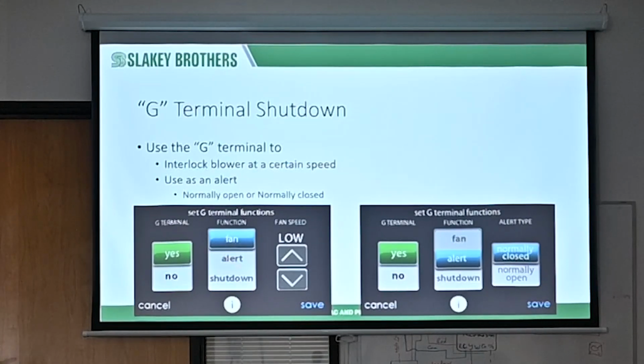The G terminal shutdown does a few different things. Okay? A G terminal, or G terminal, does a fan, which means you've got a steam humidifier that's going to throw steam into the room or into the ductwork, but it needs airflow. So you're going to use your own control because you want to use that control for that humidifier. That control just uses a dry relay. It's simply going to close R to G. Takes R to G together, and in this situation, when this fan comes on, they're going to tell it what fan speed to do. You're going to enable it. You're going to tell it you want the fan to come on. You're going to set the fan speed low, medium, or high. And then now you've got steam coming into the house. I mean, humidity coming into the home.